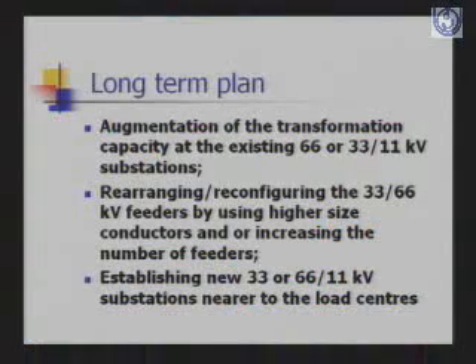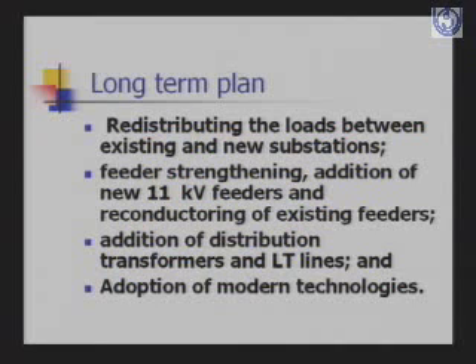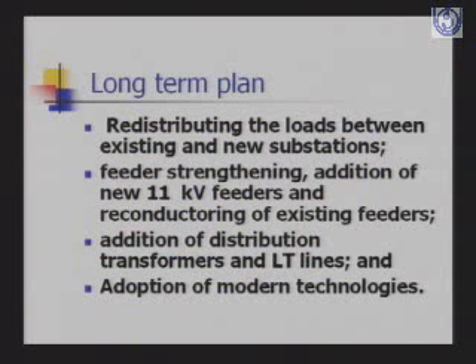So when you prepare the long-term plan, you will have to carry out augmentation of the transformer capacity at the existing 66 or 33 by 11 kV substations. You will have to rearrange, reconfigure the 33 or 66 kV feeders by using higher size conductors or by increasing the number of feeders. You will also have to establish new 33 or 66 by 11 kV substations nearer to the load centers. All these three have to be considered while preparing the long-term plan. You will redistribute the load between the existing and new substations, carry out feeder strengthening, addition of new 11 kV feeders and reconductoring of existing feeders, addition of distribution transformers and LT lines, and also adopt modern technologies.